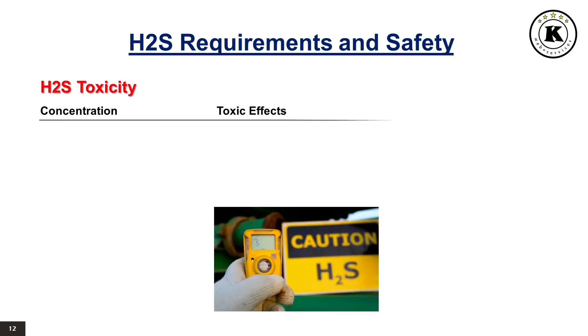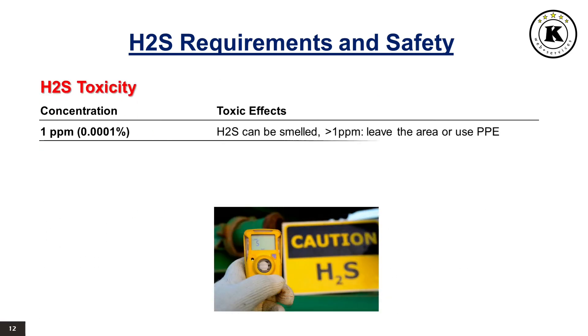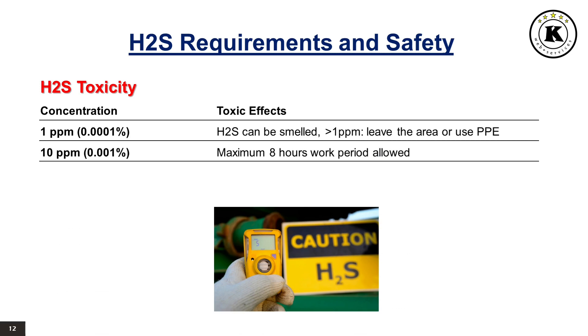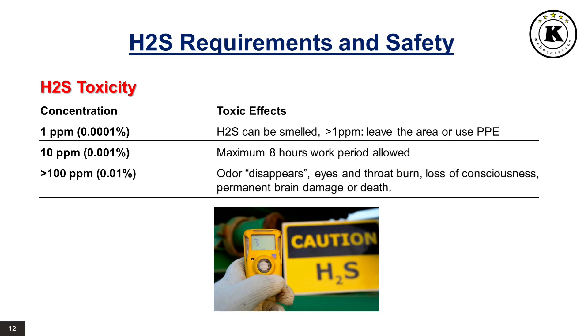H2S toxicity: At 1 ppm concentration (0.0001%), H2S can be smelled — if more than 1 ppm, leave the area or use PPE. At 10 ppm (0.001%), a maximum 8-hour work period is allowed. If the H2S concentration is more than 100 ppm (0.01%), the odor disappears, the eyes and throat burn, and there is loss of consciousness, permanent brain damage, or death.